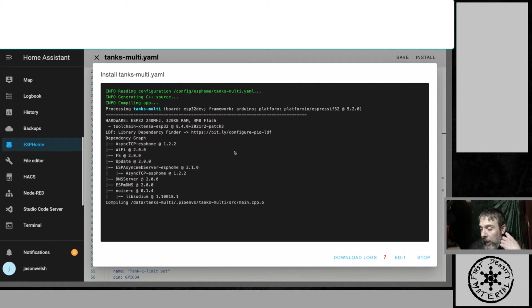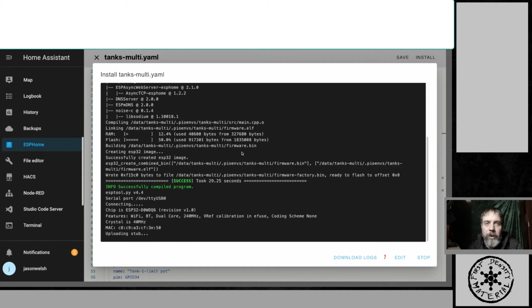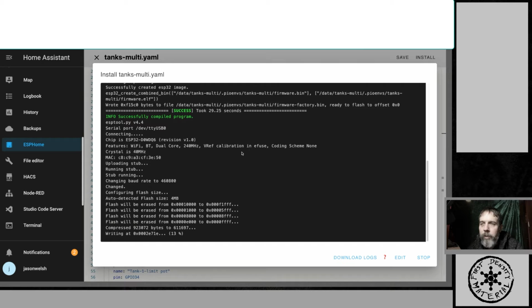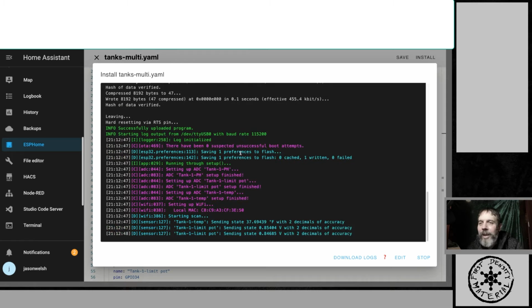So you now should be able to take that probe and put it in one of the solutions that's 6.86, and it'll be about 6.86, and the other one will be about 8 if it's baking soda. Now it's going to range too, because pH is also dictated by the temperature of the solution. So if it's real high or real low, it changes the pH value of things, which is going to be really fun when it comes down to electroforming tanks, because electroforming tanks are at 70 to 80 degrees. And in Michigan, I would say that's on the low side sometimes.